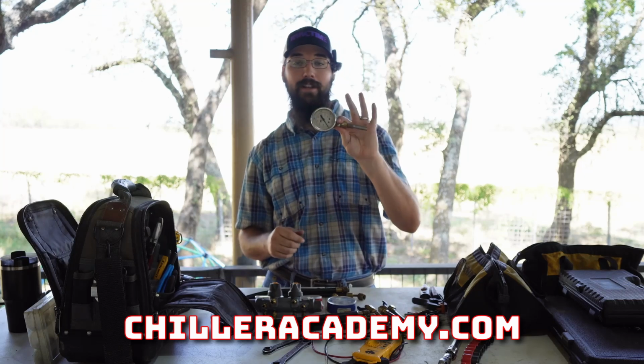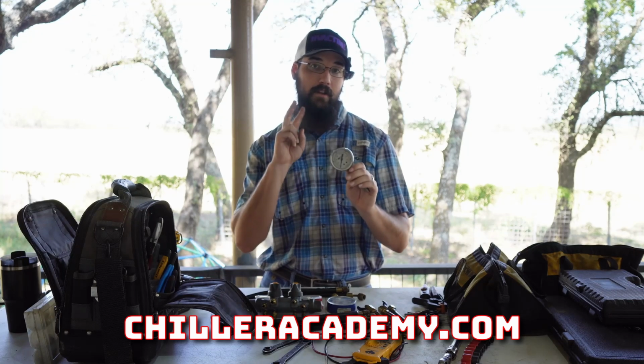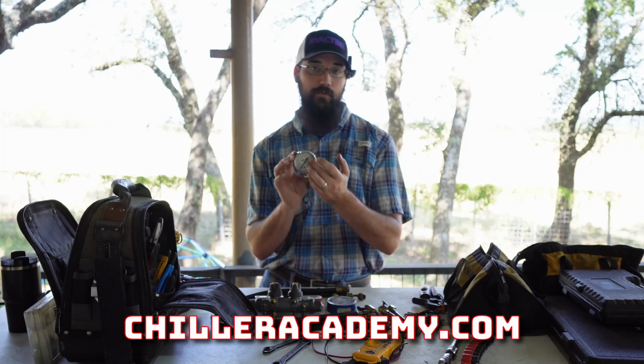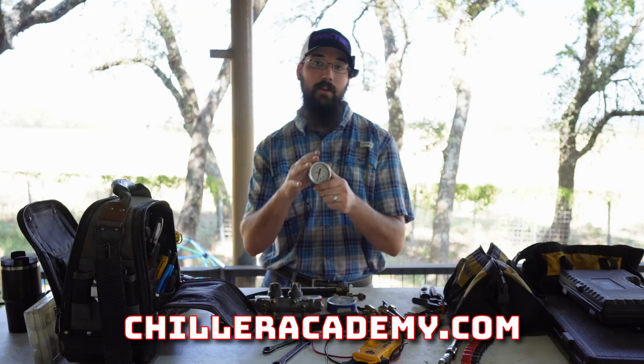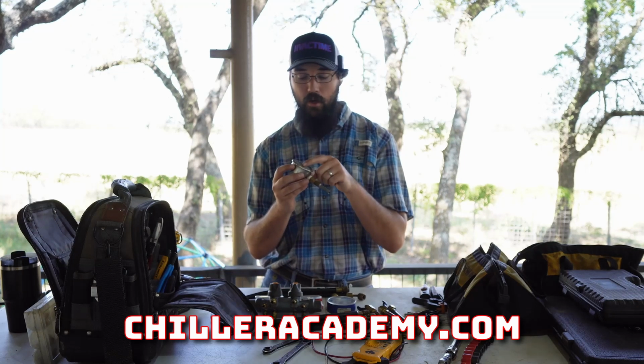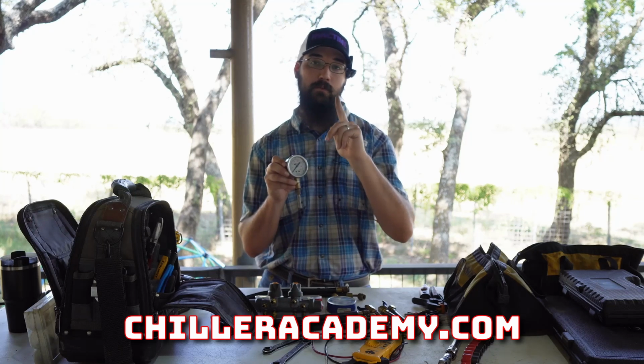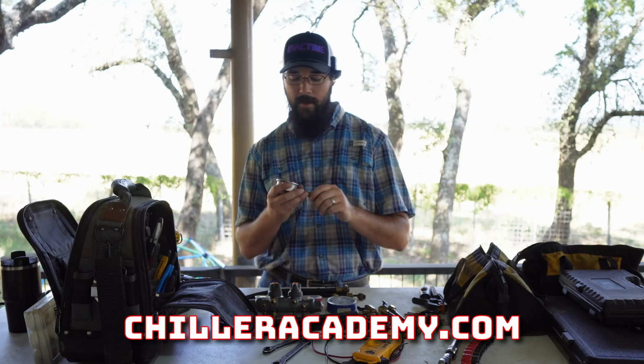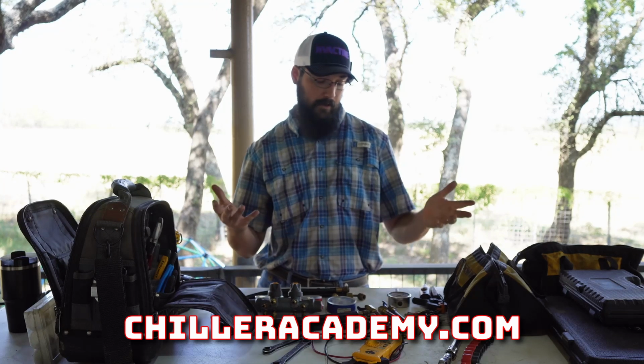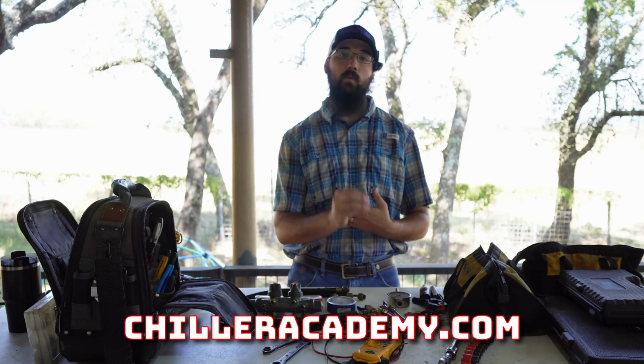Now, this particular one is also glycol filled. It is fluid filled. I do recommend that. It does two things. One, these are typically a sturdier build because they have to hold the fluid, so for that reason, I've had better longevity out of these versus the dry version. They also remove the flutter. Sometimes the needle can flutter a bit as it's moving around depending on the circumstances. Having the glycol in there helps reduce that flutter to where it's either very minimal or not even there at all, when it would be if it wasn't glycol filled.